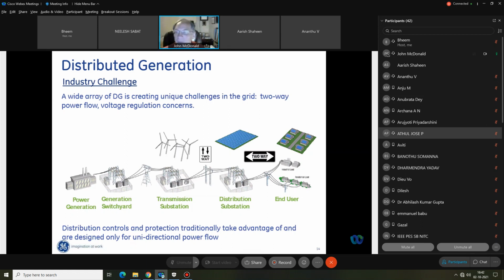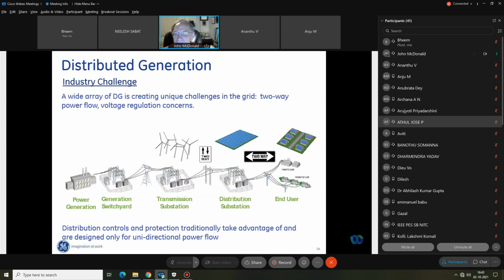In other words, for many years, if you were a field worker with an electric utility and you were going to go out to do some work on the distribution part of the grid, the rule was that before you did the work, if you opened the upstream device only, like a switch, then you had a safe working situation, because now everything downstream was de-energized, because electricity flowed in one direction only, from source to load.